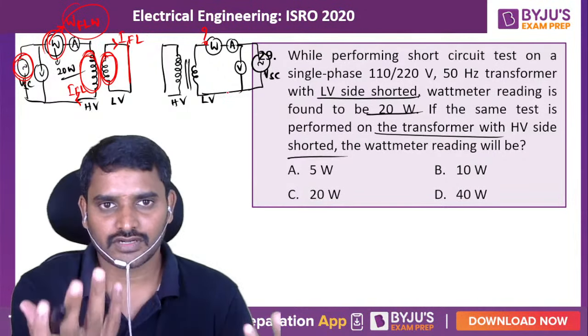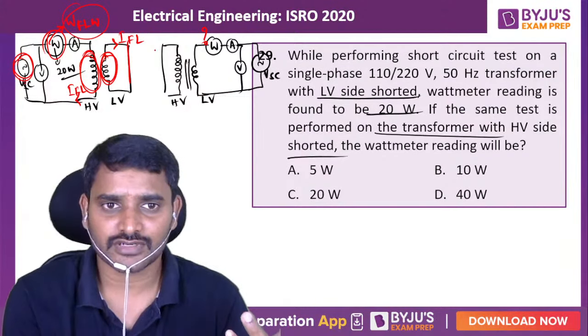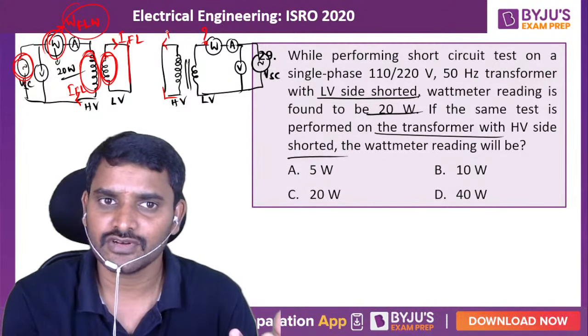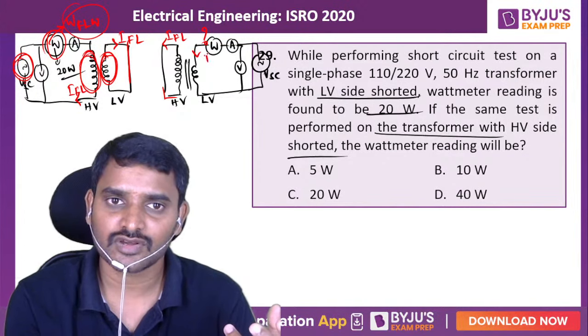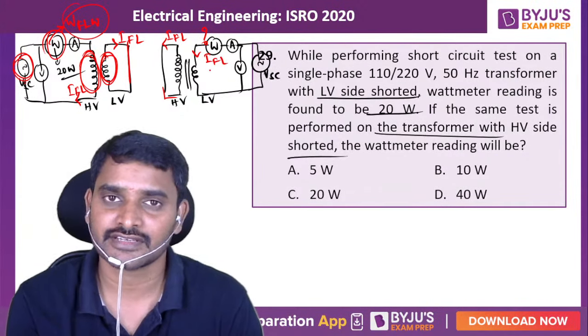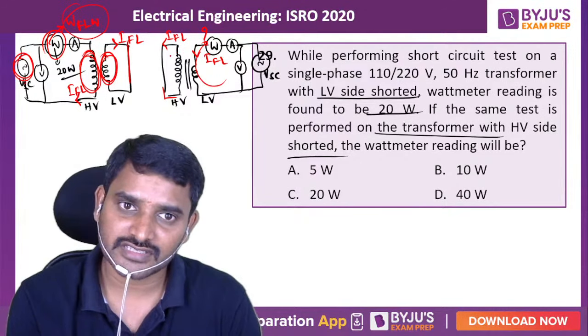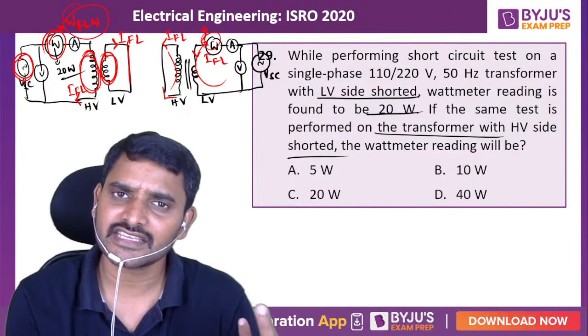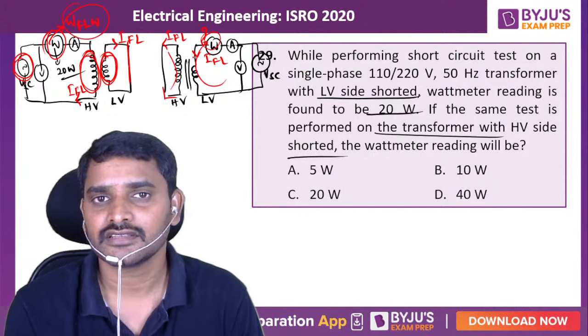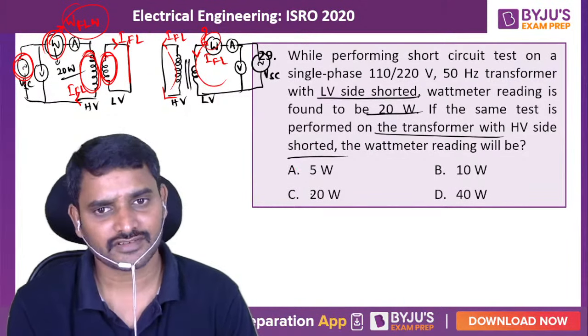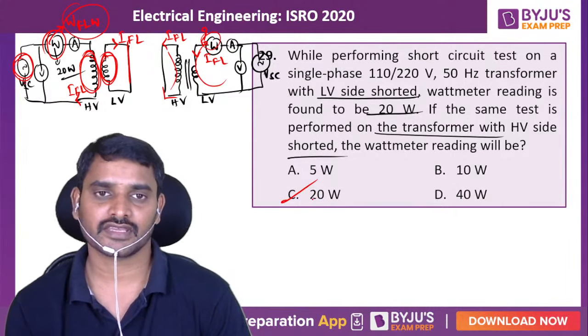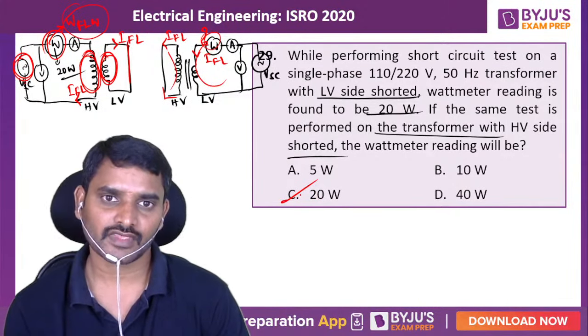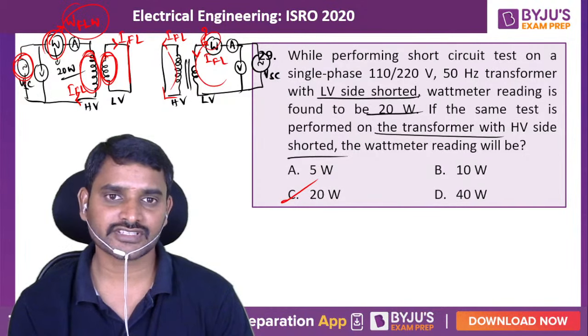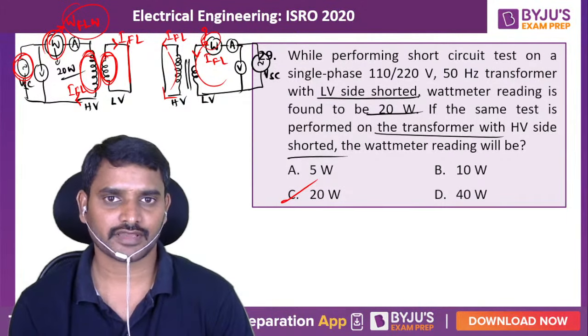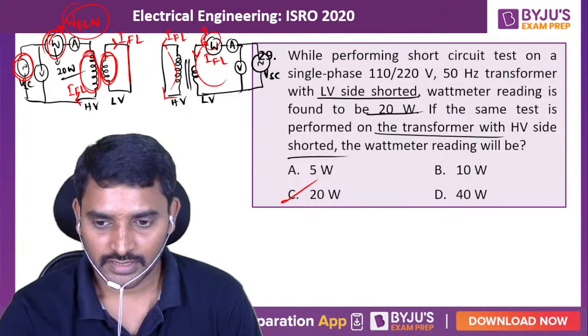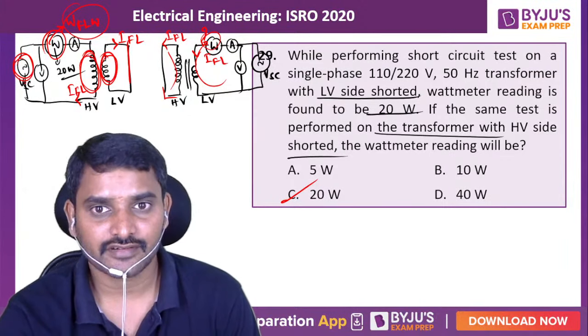And whichever winding you short circuit, if you short circuit the high voltage winding, full load current will circulate. Here also, in the low voltage winding, full load current will circulate. So here also rated copper losses, here also rated copper losses. Then the wattmeter again indicates rated copper losses only. There is no big difference in the wattmeter reading. It will again indicate the same 20 watts. Does it make any difference? The wattmeter will show the same losses. Okay. 20 watts.